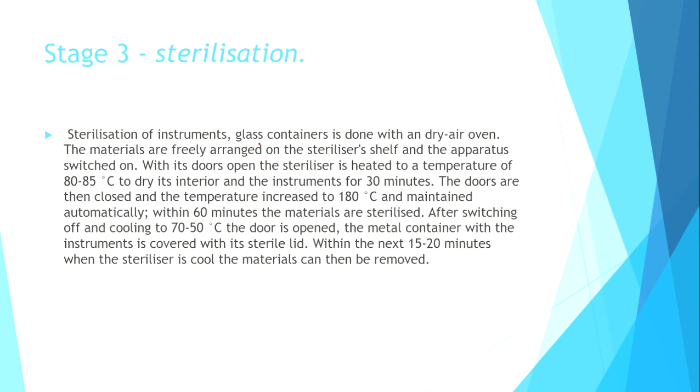The doors are then closed and the temperature increased to 180 degrees Celsius and maintained automatically. Within 60 minutes, the materials are sterilized. After switching off and cooling to 70 or 50 degrees Celsius, the door is opened. The metal container with the instruments is covered with its sterile lid. Within the next 15 to 20 minutes, when the sterilizer is cool, the materials can then be removed.